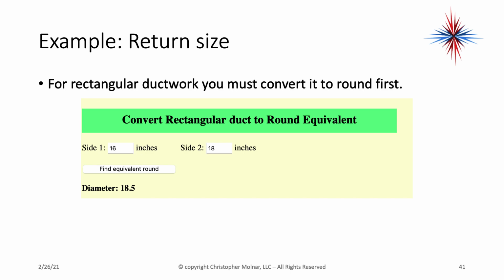For rectangular ductwork, you have to convert it to round first. The same online tool will let you do this. Okay, you enter side 1 and side 2, find the equivalent round, 18.5. Okay, remember that 18.5 was the magic number. You'll never have 18.5 inch round ductwork. You'll go to 19 or 20, depending on what's available at the supply house. But if it's smaller than that, you have a problem.